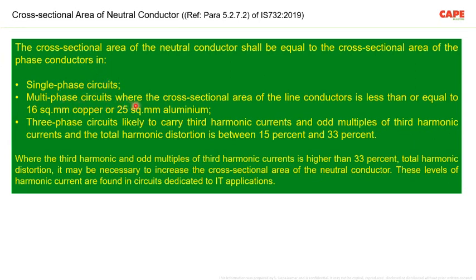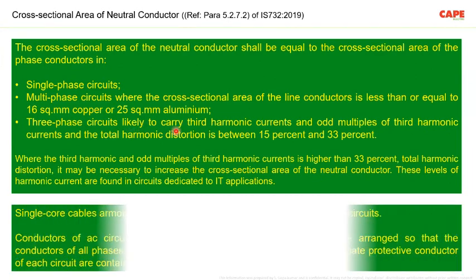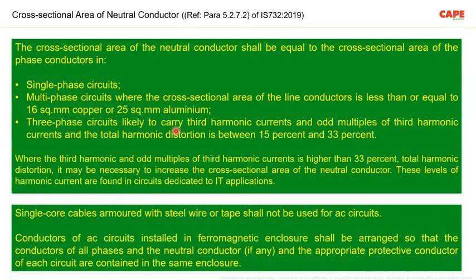phase circuits and multi-phase circuits, where the cross-sectional area of the phase is up to 16 square mm copper, then the neutral also must be 16 square mm. More than that, there are some exceptions. So you also should consider harmonics in the case of the neutral conductor.